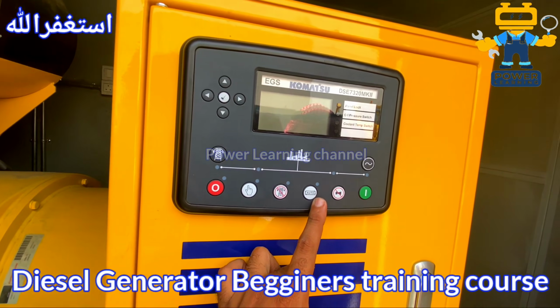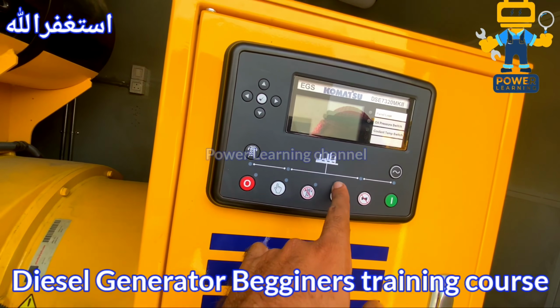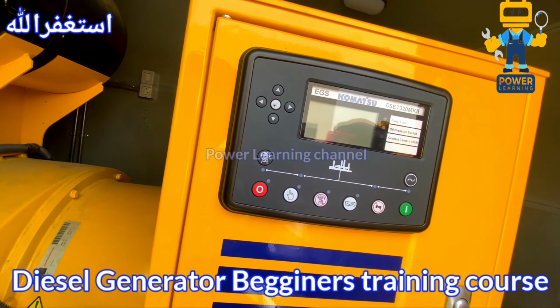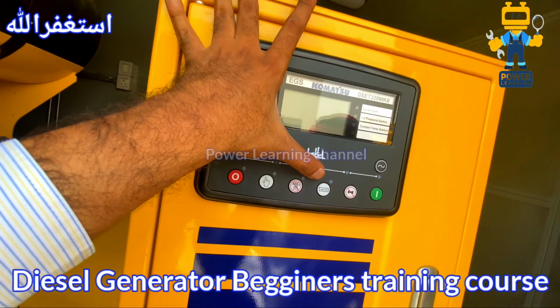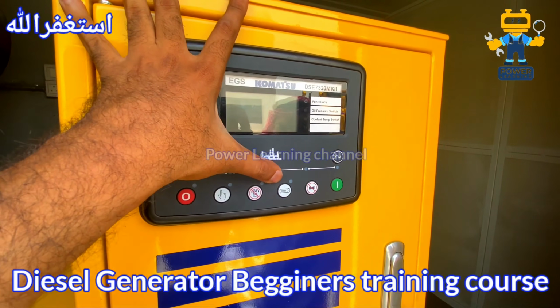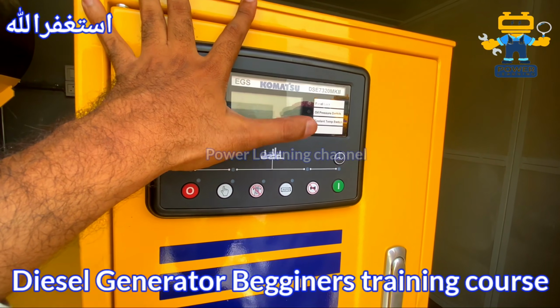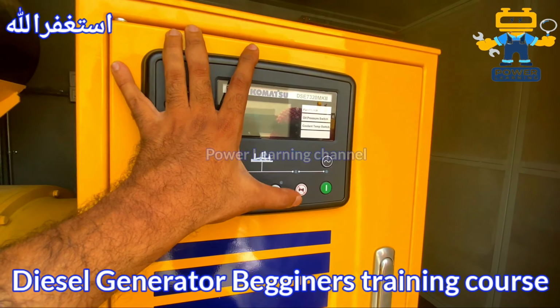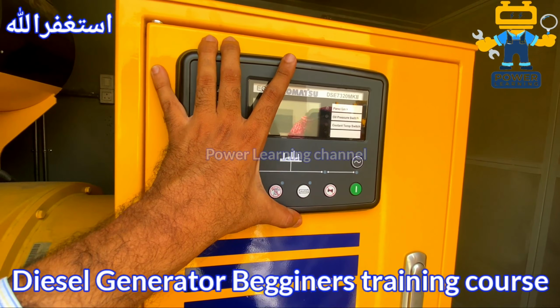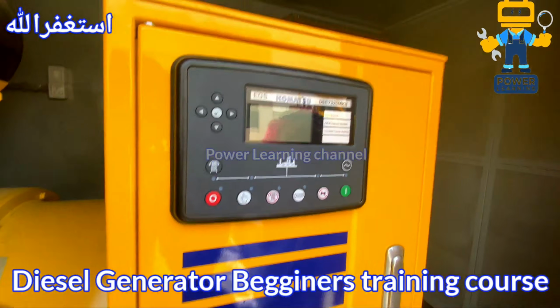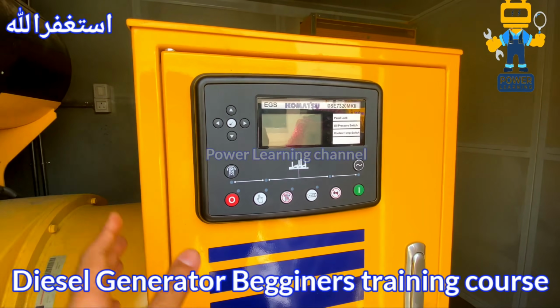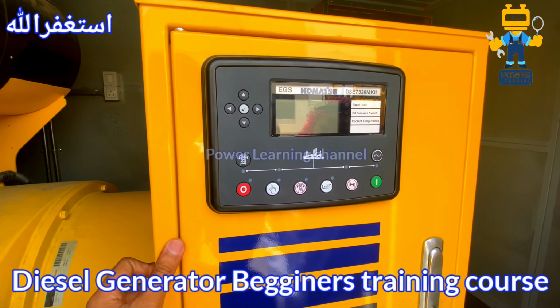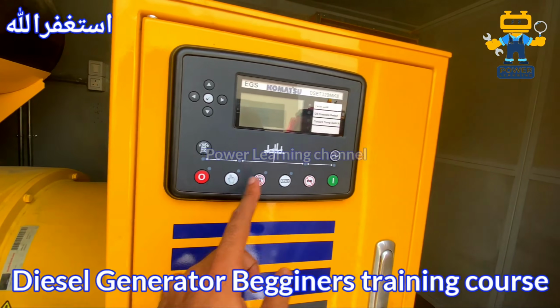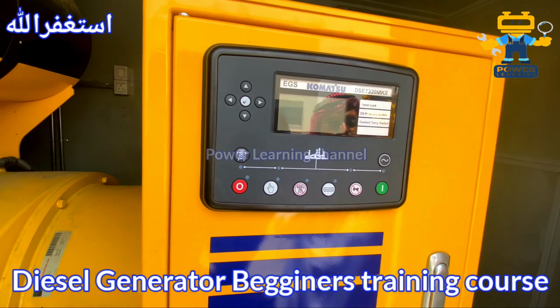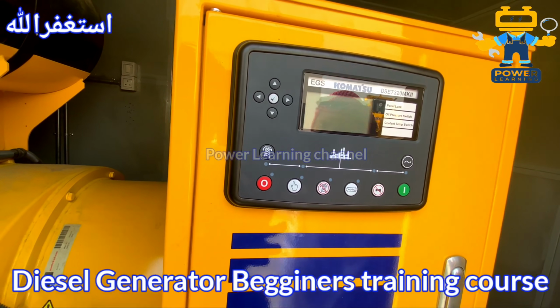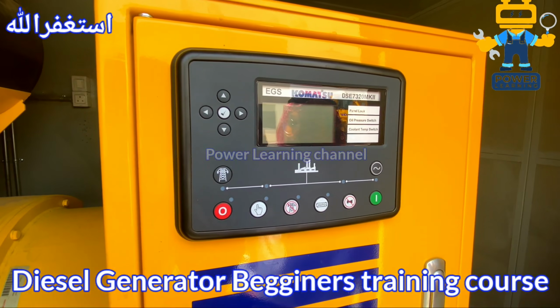This is the auto button. If you select this button, you must have an ATS panel, which will automatically give a signal to this controller, so this controller will start the engine. Is this the half ATS? No, the ATS should be separate. It depends on the customer side. For example, if the customer doesn't have utility power, they will use it manually. If this is emergency power, they will use an ATS panel.